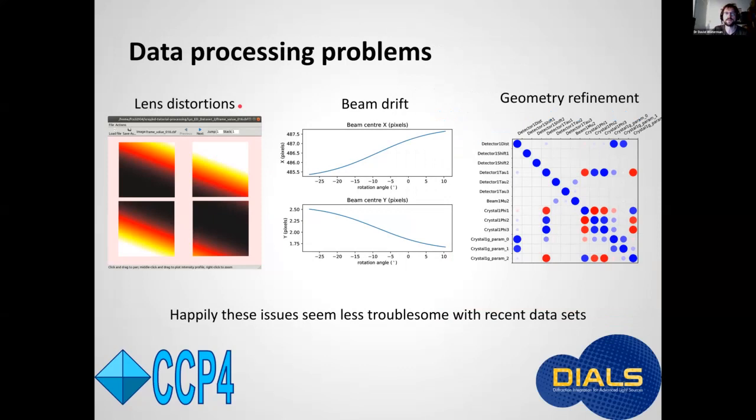Processing that data showed numerous problems that we had to address in order to get dials to work. So first, the lenses in electron microscopes may introduce distortions into the diffraction patterns. And dials is a program that was born in the era of hybrid pixel array detectors and it didn't have the means to correct distortions. So we had to add that first.